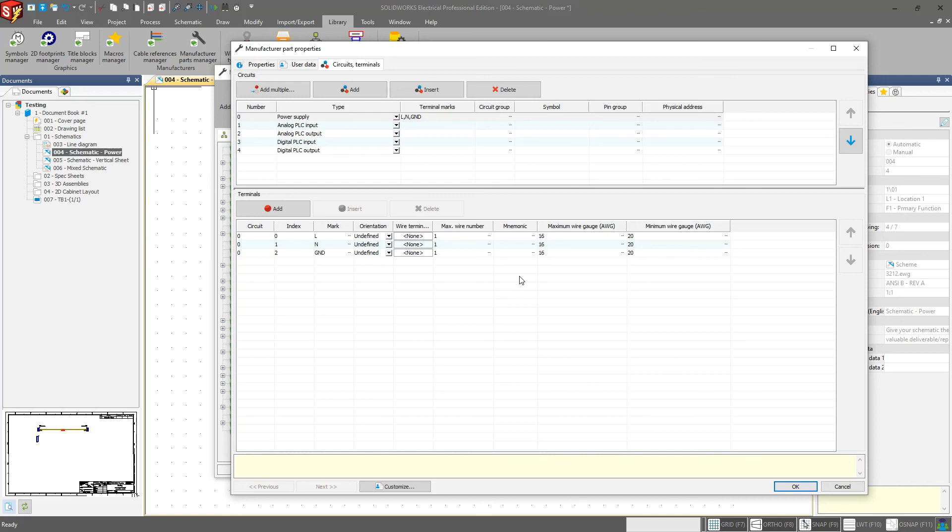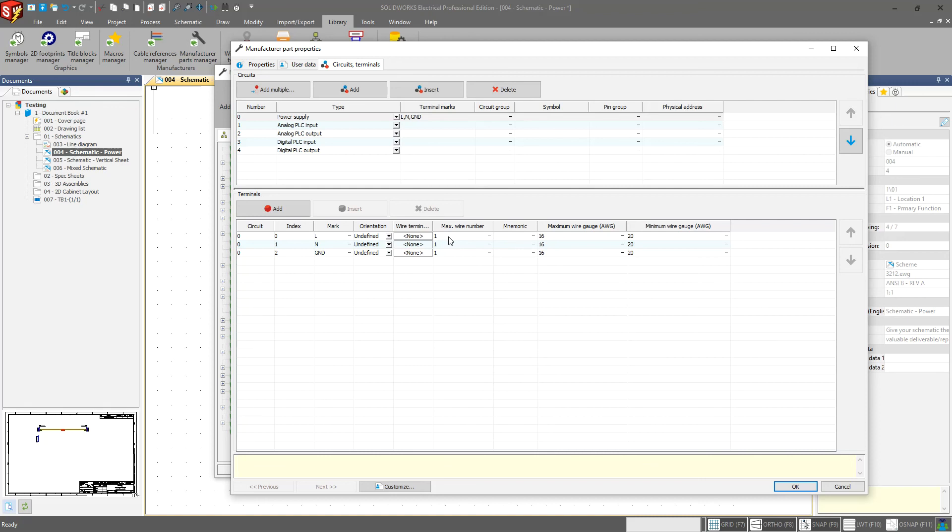Maybe I am going to be using for my max gauge. Maybe it's 16 is the max. And 20 is the min for this. So these are additional design rule checks that you can run, or, you know, maybe in your schematic, you were getting something done real quick and you were using a 14 gauge wire for whatever reason, and you hooked it up to your PLC and now you can run this report and hey, whoa, red flag. The PLC says that the maximum gauge is only 16, but in my schematic, I have a 14 gauge wire running to it. Let me go back and check that. So now these are some things, you know, same thing applies to the max wire number. Maybe I inadvertently added two wires to the same terminal, you know, but the PLC says you shouldn't do that because of whatever reason. It's not designed to do that. So you can set these to one, you can set these to whatever you want. If you want to be able to put 10 wires in there, have at it. But, you know, we all know that's probably not the case in most cases.